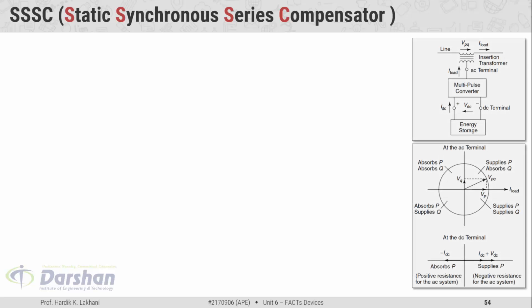SSSC is Static Synchronous Series Compensator, sometimes also called S3C. This is the line diagram of SSSC and below that the power exchange diagram is shown. In the construction of SSSC, a Multi-Pulse Converter is used along with an Energy Storage Component. This SSSC is connected to the power system with the help of a Coupling Transformer, and this compensator is connected in series with the line. That is the major difference between the STATCOM and the SSSC — the STATCOM is normally connected in shunt manner, but this compensator is connected in series manner.